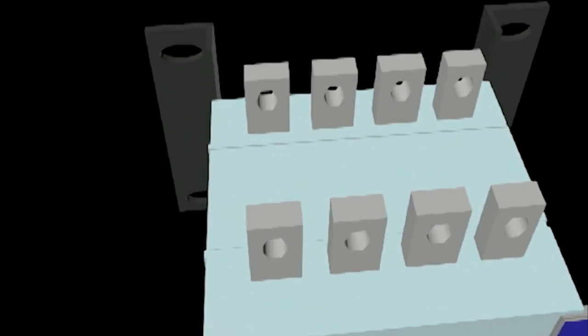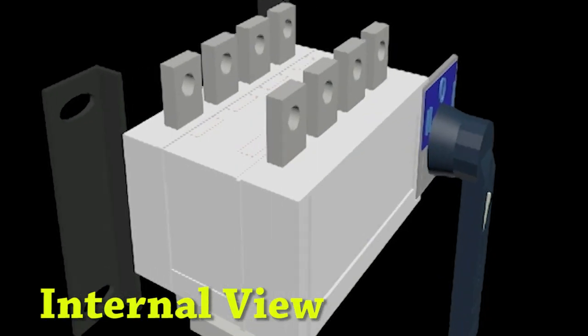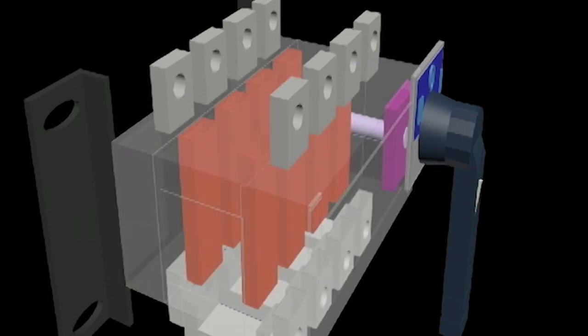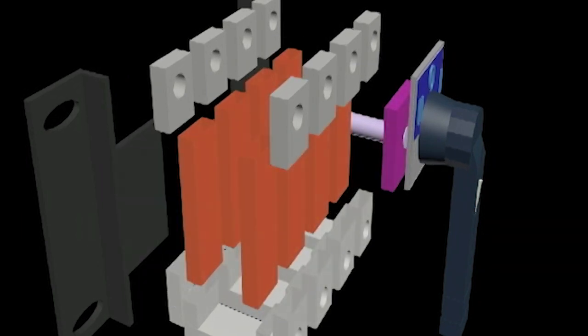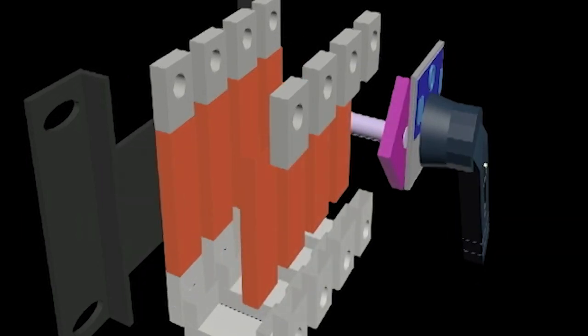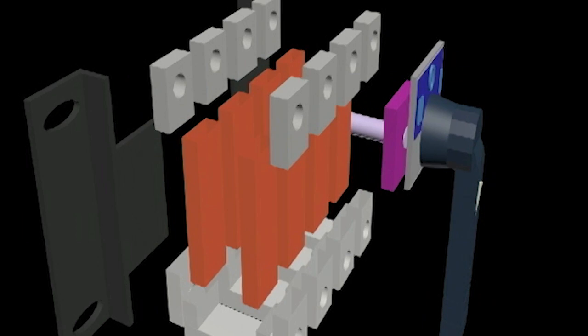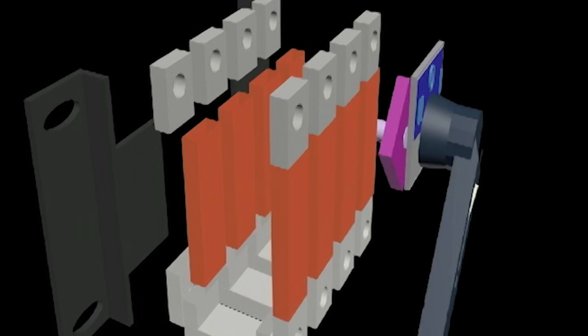Let us see its internal view to understand its working. When the handle is rotated to position 2, the lower side terminals get shorted to the upper side position 2 terminals. When the handle is rotated to position 0, the internal shorting disconnects. And if the handle is rotated to position 1, then the lower side terminals get shorted to the upper side position 1 terminals.